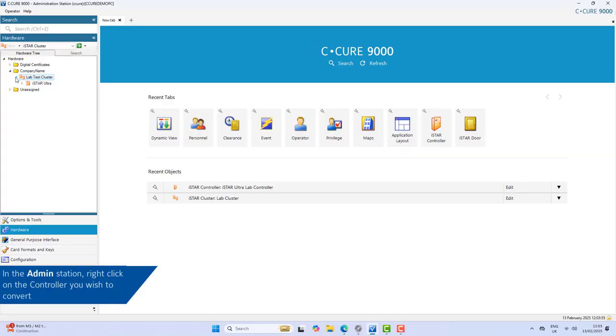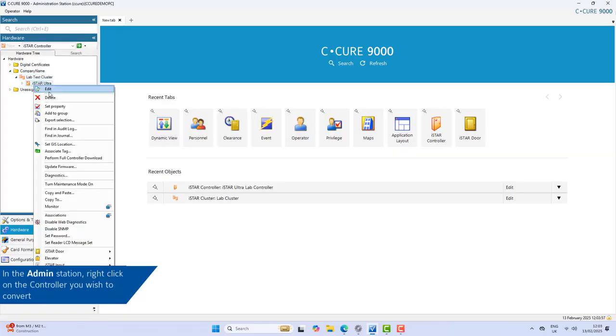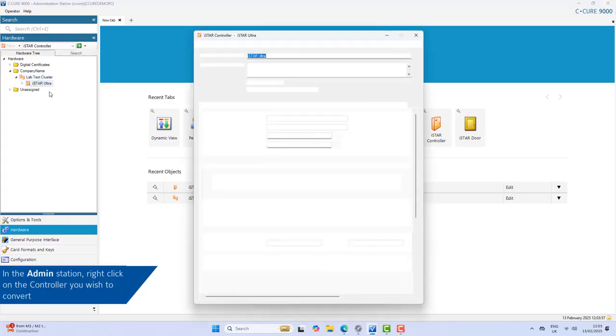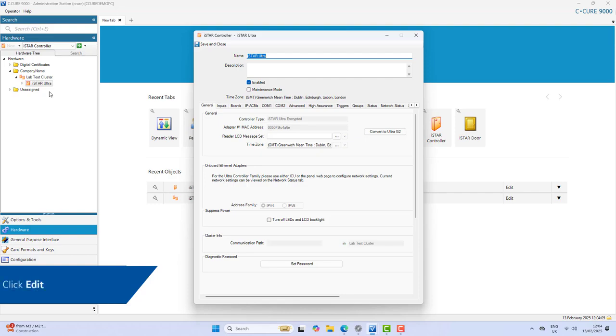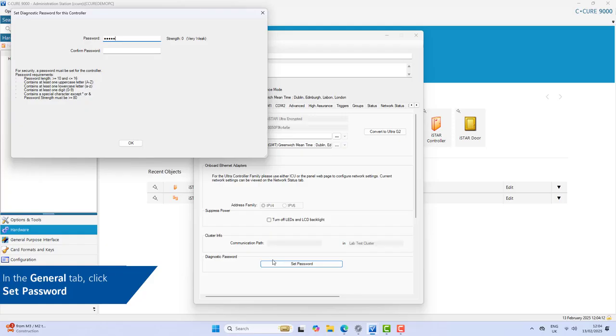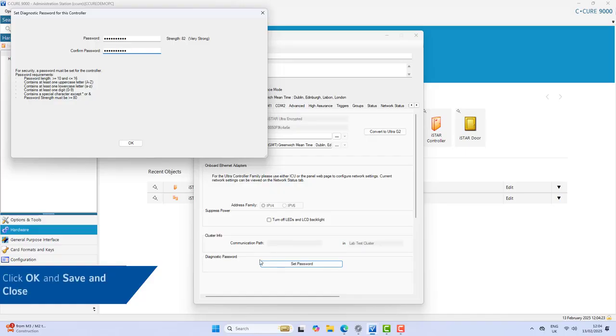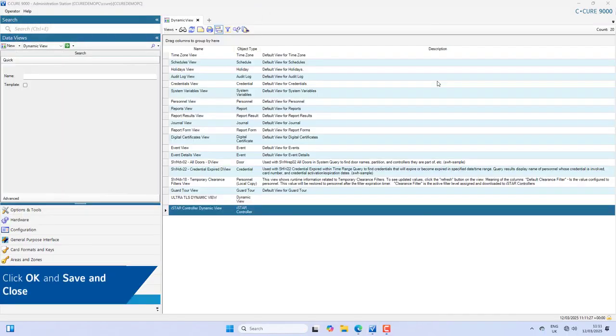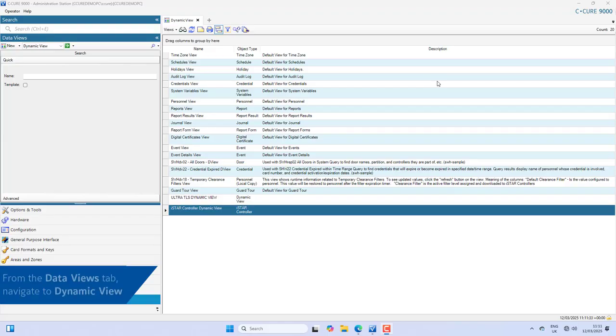From an administration workstation, complete the following steps for every controller in the cluster: edit the controller, click Set Password, set a password for the controller, click Save and Close. From the admin station, ensure all iStar controllers in the cluster you're working on are online and communicating. From the Data Views tab, navigate to Dynamic View.